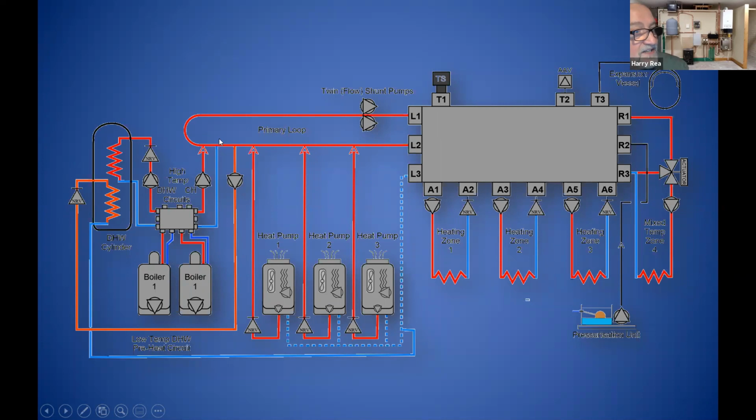At this point, it's taken down into an NRG 4, a little small standard manifold. There are 2 35 kilowatt gas boilers underneath. We're taking the water heated by the heat pump, and in the coldest of weather, our weather compensation manifold turns on the gas boilers. We're taking the same water and putting it up to 60 or 70 or 80 degrees, whatever is necessary for weather compensation.